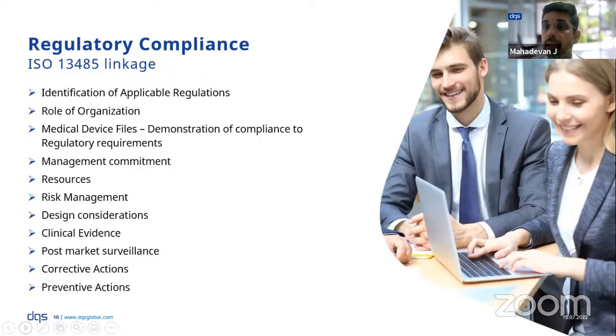Design considerations: whatever the regulatory requirements are, they need to be taken in as design input. Examples are applicable standards to demonstrate state-of-the-art, benchmarking to demonstrate state-of-the-art, and labeling requirements based on the regulatory requirements. These have to be considered as part of design input. Instructions for use, whatever is required to use the device safely and effectively. There are requirements in multiple regulations. Those things need to be part of your input so that you provide those instructions appropriately. So various design considerations come in from the regulatory aspects as well.